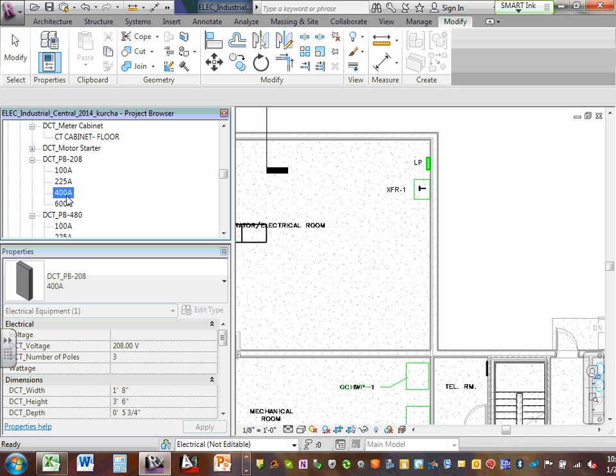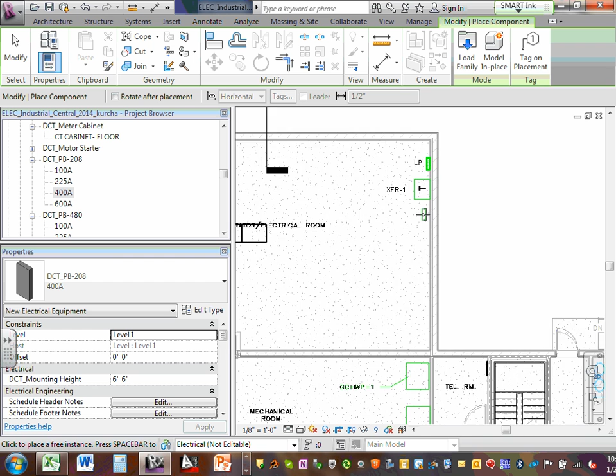Yeah, we're going to the 208 distribution panel. We need 300. There is no 300, we'll go to the 400. Grab one, situate it, and put it right next to the transformer, right here, and tag it. Annotate, tag, synchronize, save project, yes, save.